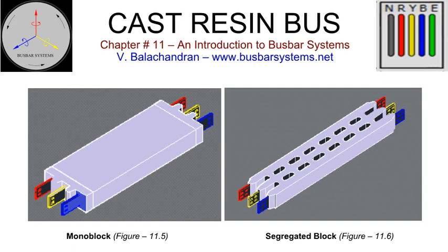Such a configuration has several advantages: reduces voltage stress on the insulation, saves the quantity of epoxy and is hence economical, makes the cast resin bus light, makes heat dissipation more efficient, thereby enabling a higher current rating. A well-ventilated aluminium enclosure can be fixed to the cast resin bus to protect it from damage after installation, contain the stray magnetic field within the enclosure which acts as a shield, provide weather shield when located outdoors, above ground, facilitate the installation of resin cast assembly on the support structure, facilitate the installation of an external earth bus on the enclosure. The reactance of the conductor will increase with the increase in the phase spacing. This is not of much consequence in a medium voltage cast resin bus.